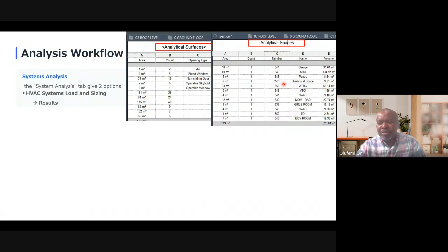It will also give you a space ventilation schedule following the ASHRAE standard. You can see the breathing zone (VBZ), the required air by floor area, required air by person based on the recommended space type, and it will calculate the ventilation air required for those spaces.